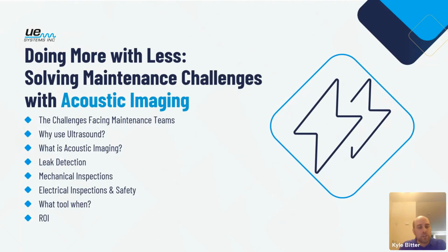With acoustic imaging, there are a couple main applications we'll discuss here today. The first is leak detection for both compressed air and gas, as well as quantification of those leak detection efforts. Also mechanical inspections - we have the ability to utilize acoustic imaging for mechanical inspections, pointing out bad bearings, trouble spots within conveyor belts, and things like that.